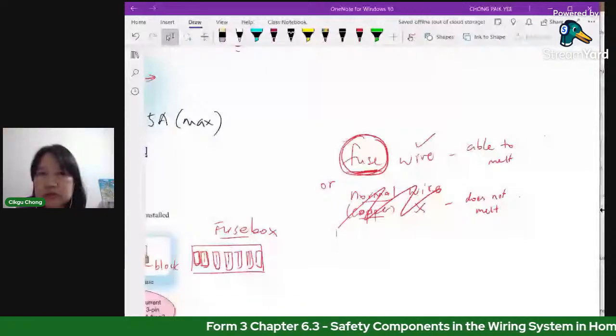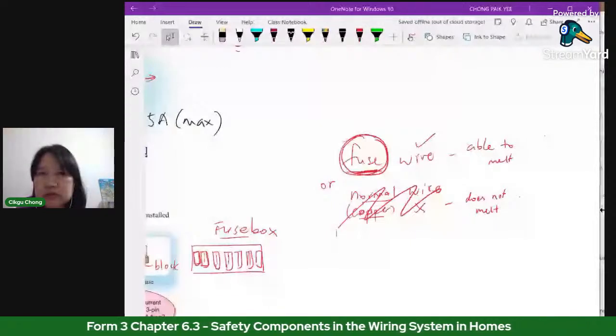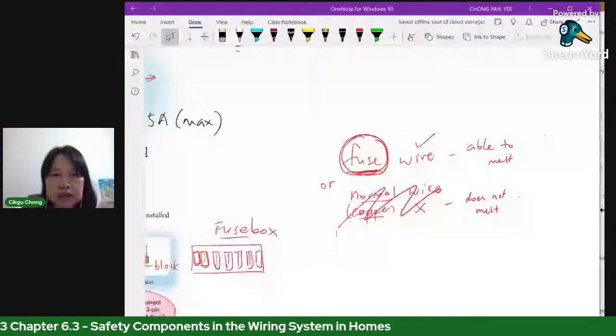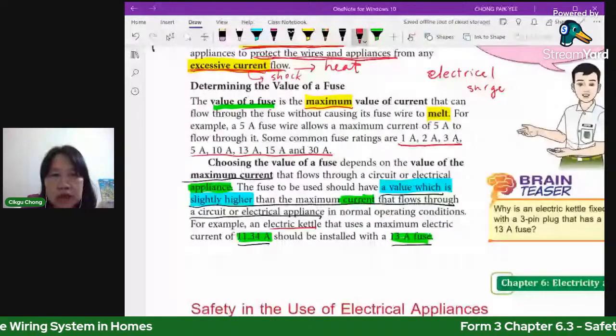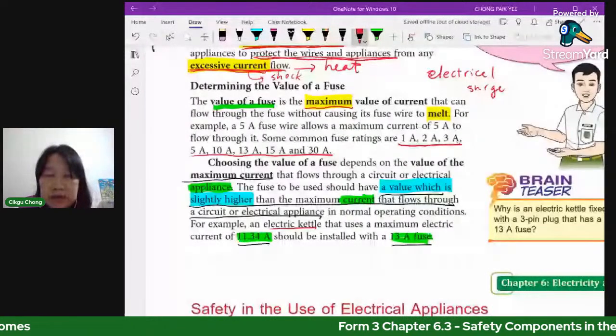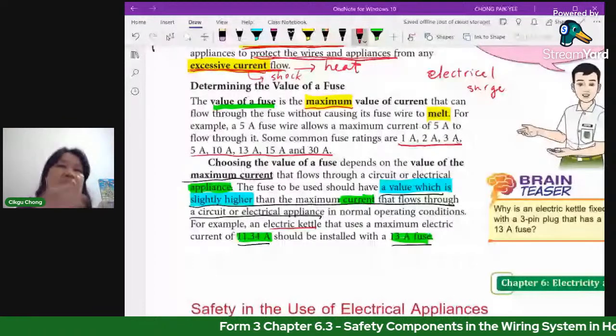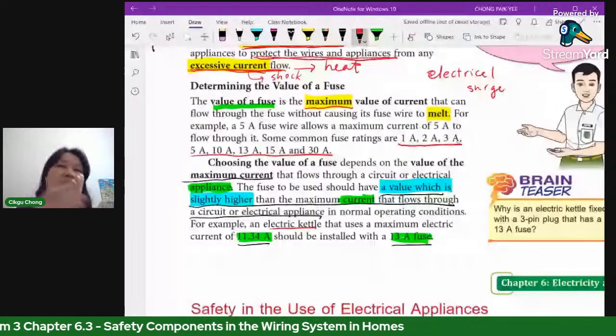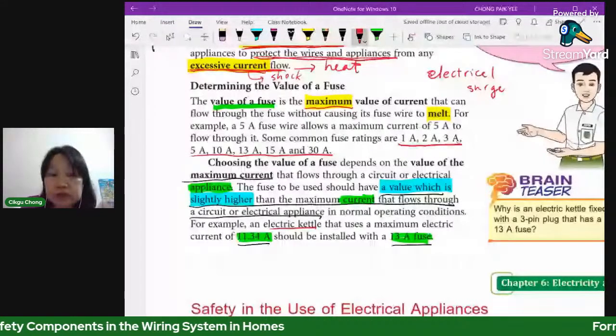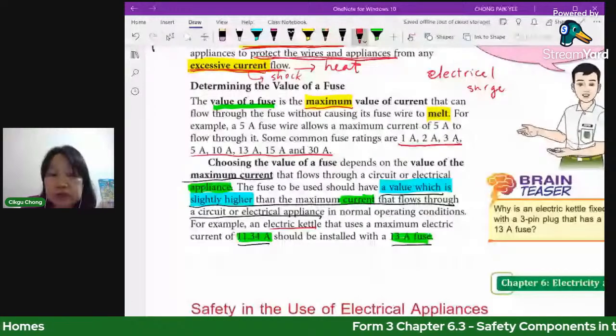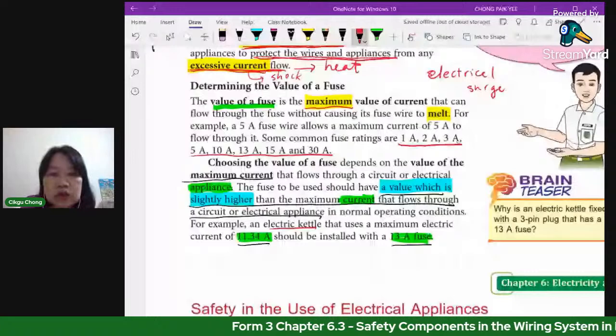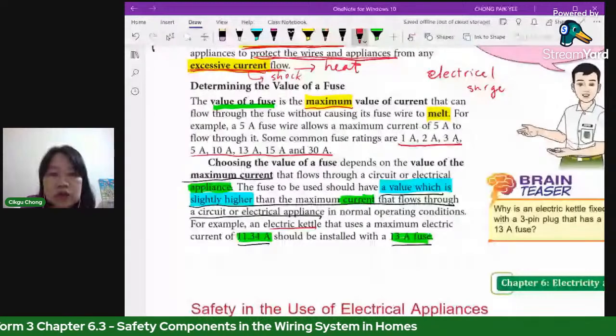For example, if your electrical kettle uses a maximum current of 11.34 amperes to boil water, the fuse you use must be a little bit higher than that. So you don't put something lower than 11, you put something higher, but just slightly higher, not too high.